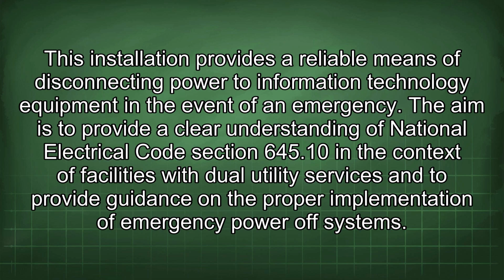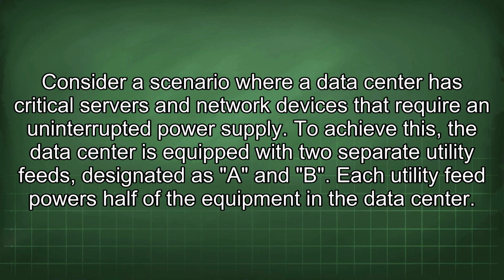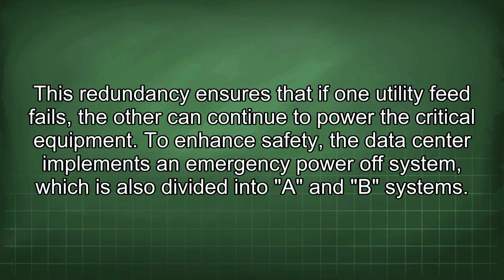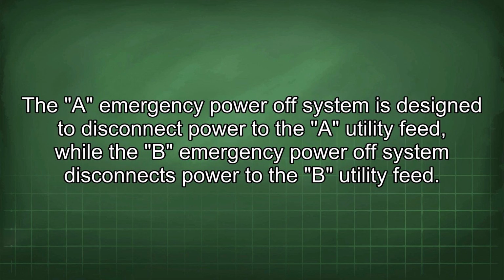Consider a scenario where a data center has critical servers and network devices that require an uninterrupted power supply. To achieve this, the data center is equipped with two separate utility feeds, designated as A and B. Each utility feed powers half of the equipment in the data center. This redundancy ensures that if one utility feed fails, the other can continue to power the critical equipment. To enhance safety, the data center implements an emergency power-off system, which is also divided into A and B systems. The A emergency power-off system is designed to disconnect power to the A utility feed, while the B emergency power-off system disconnects power to the B utility feed.